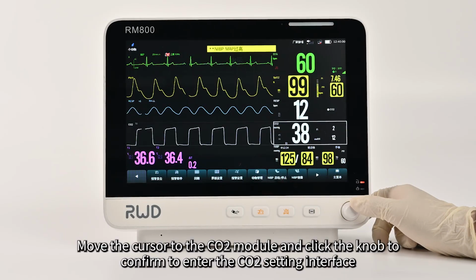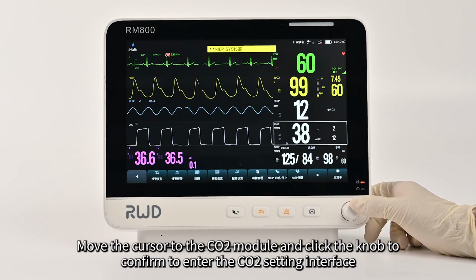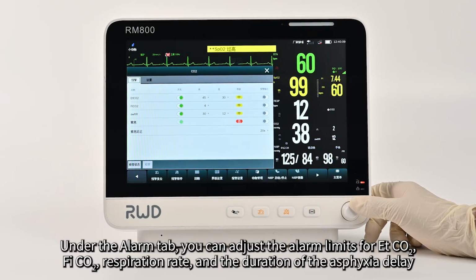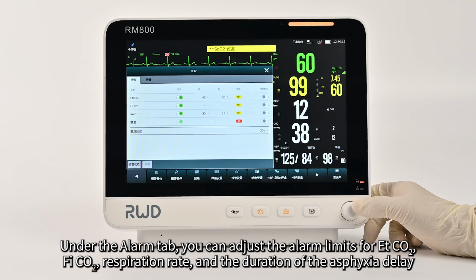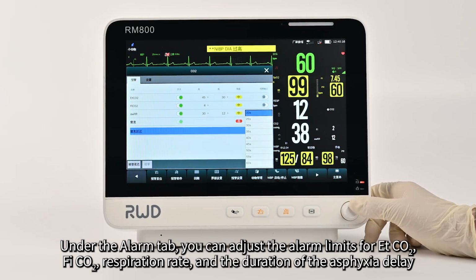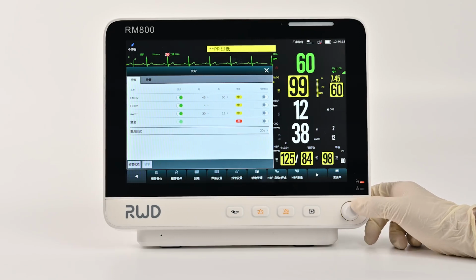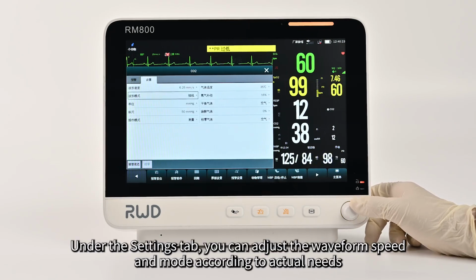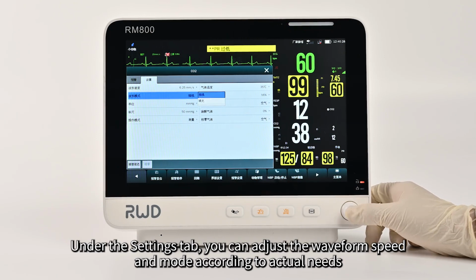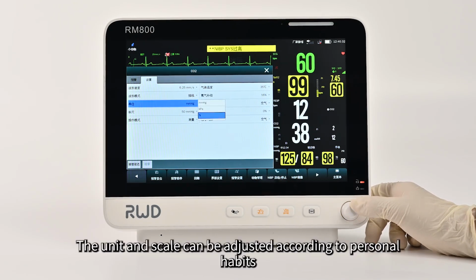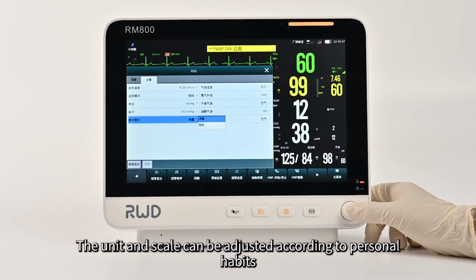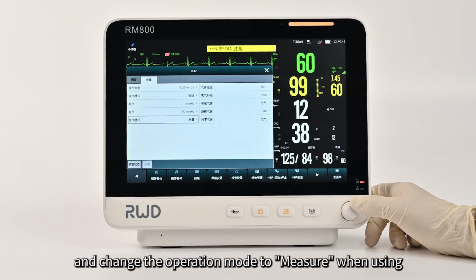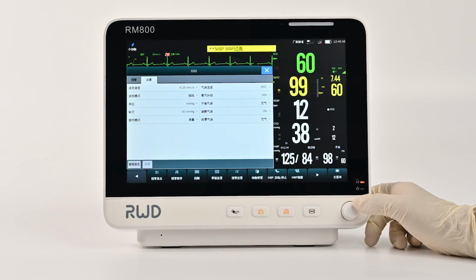Move the cursor to the carbon dioxide module and click the knob to confirm to enter the carbon dioxide setting interface. Under the Alarm tab, you can adjust the alarm limits for end-tidal carbon dioxide, inhaled carbon dioxide, respiration rate, and the duration of the asphyxia delay. Under the Settings tab, you can adjust the waveform speed and mode according to actual needs. The unit and scale can be adjusted according to personal habits, and change the operation mode to measure when using.